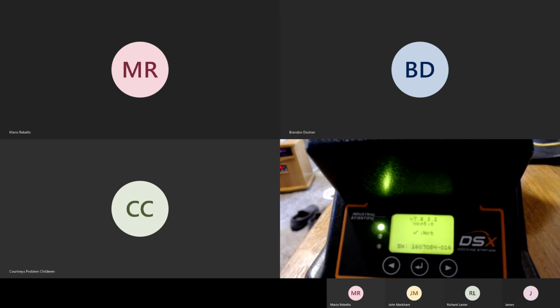Okay. So with that red light, it's very simple. What we do is we just stop, we wait, and we take a look at the error message that comes across on the screen. A lot of times it's something very simple that can be fixed. Like it'll say out of gas, because the bottle ran out during the test. Or if it's a failed calibration, what I would always recommend at that point is pull the instrument out, turn it on, and take a look at what sensors failed. So, looking at your instruments, it looks like the sensor configuration that you have is the LEL, HCN, O2, H2S, and CO.